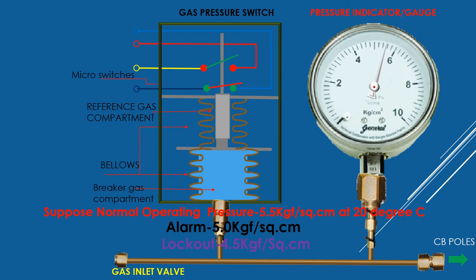There is a pressure switch which makes and breaks contact at particular pressure values when the gas inside the poles reaches below certain values — at 5.0 kgf per centimeter square and 4.5 kgf per centimeter square — by striking the tappet head. These contacts are connected electrically with alarm circuits and contactors situated outside to produce an alarm and to disconnect circuits as a protective measure. In the event of lockout, the circuit breaker should not be either closed or opened, so contactor 63GL actuates to disconnect the closing circuit as well as the tripping circuit.